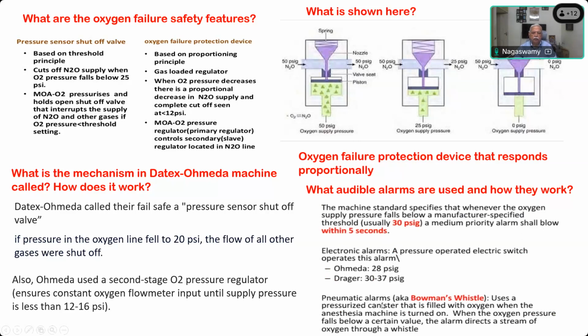A pneumatic alarm, also known as Bowman's whistle, uses a pressurized canister that is filled with oxygen when the anesthesia machine is turned on. When the oxygen pressure starts falling below a certain level, the alarm directs a stream of oxygen from the canister out through a hole, which causes the whistle sound. How long should that whistle continue? Minimum 15 to 20 seconds, so that it can be identified.